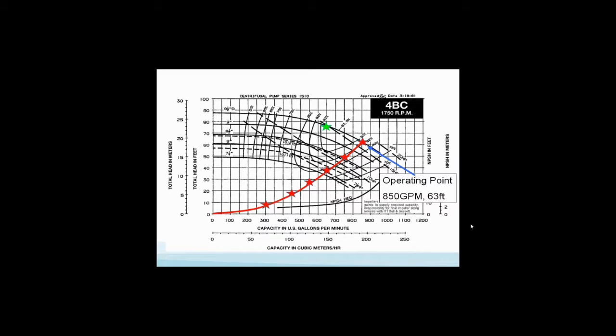But we're pumping too much water. Wouldn't it be nice to save some money here? So what do we do now? How much flow do you want? The design flow was what? 650 GPM at 76 feet of head was design flow. All we do is do a little vertical line, and where that vertical blue line crosses the red system curve is our minimum impeller size required to give you 650 GPM, which I think you're going to find is about 37 feet of head. But notice the brake horsepower.